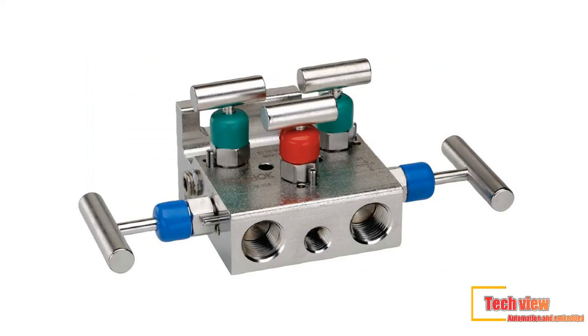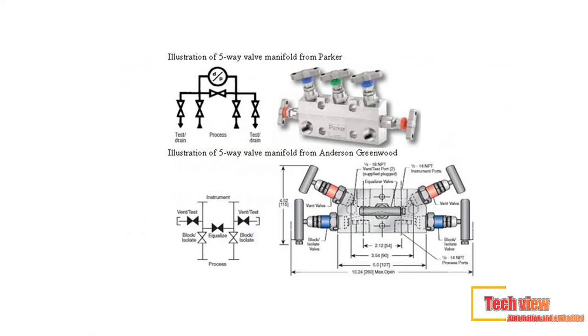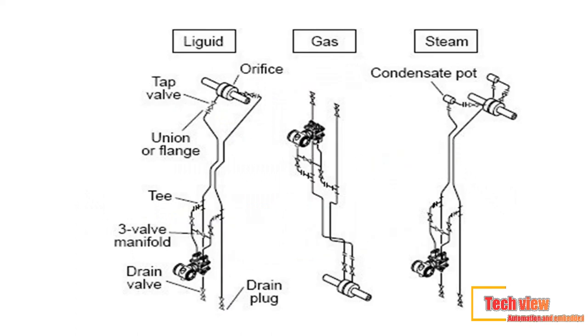Calibration issues can be important to the successful application of this technology. Differential pressure transmitter removal for calibration exposes the transmitter to multiple sources of potential problems that can affect the measurement, not the least of which is the extent to which the transmitter tubing is retightened after calibration. Calibration should generally be performed in situ when possible, and provisions to do so should be addressed during the design phase. For example, the differential pressure transmitter can be purchased with an integral valve manifold that allows easy calibration without disconnecting impulse tubing.